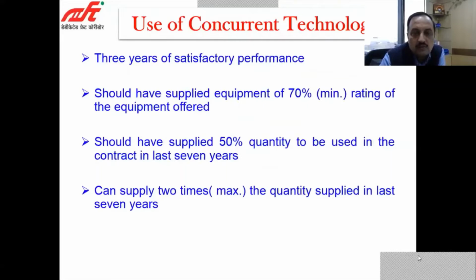These are the main aspects: the vendors who have to supply the material should have 3 years of satisfactory performance, should have supplied equipment of 70% of the rating of the equipment and 50% of the quantity in the last 7 years. And he can supply a maximum of 2 times the quantity supplied in the last 7 years. So these are the guidelines which we have adopted in our tenders for the approval of new vendors who are not approved on Indian Railways so far. It means we are quite open to new vendors also. If anyone is meeting these criteria, then he can be eligible for approval in DFCCIL corridors.